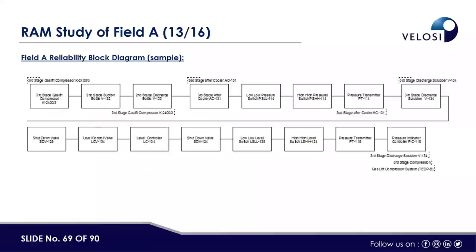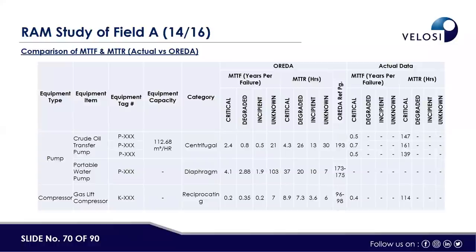A maintenance profile for critical equipment is included in the assumption table. Maintenance resources are defined — for example, for gas lift compressor critical failure: one supervisor for mechanical maintenance, two technicians, and two helpers. For electrical or instrumentation/control maintenance, no supervisors or technicians were required at that time as provided by the client. Total crew for this activity was five, number of spares required was two, and accessories needed for this failure were also specified. A screenshot of the reliability block diagram for the third-stage gas lift compressor shows the RBD before being populated with reliability data.